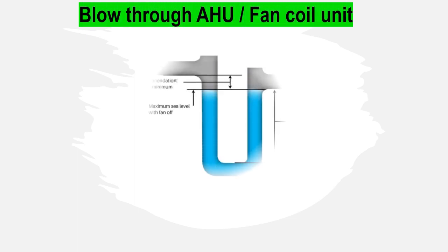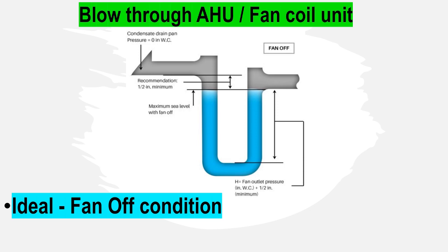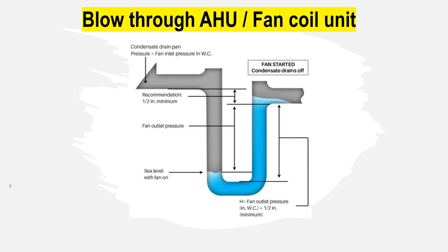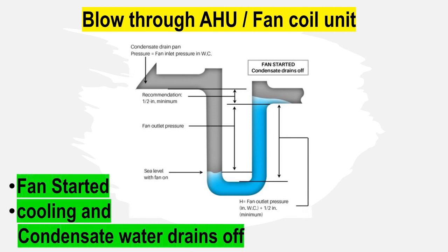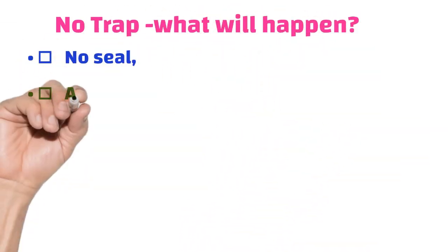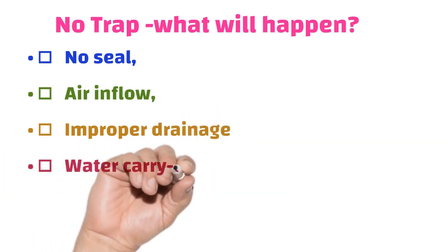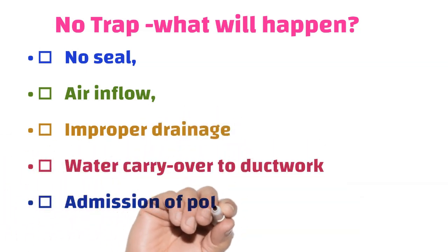For the blow-through unit at the ideal fan-off condition, both sides of the trap contain the same level of water before the fan starts and condensation begins. When cooling and condensation begin, the water starts to drain off due to positive pressure on the fan coil side, and the water is easily pushed down to drain.